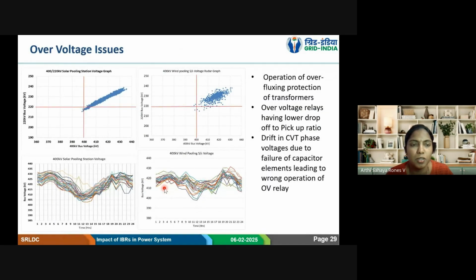And the over voltage related issues. Whenever there is no generation, if we see this solar pooling station's 400 kV voltage, during solar generation it will be like this, and the voltage is the opposite of that. So during night hours, that means non-solar hours, the voltages will be very high. And with wind also, depending on the wind availability, at other times the voltages will go high. So usually over voltages are there.